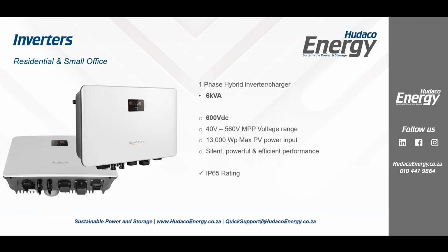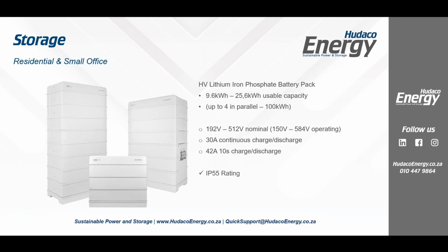600 volts DC, 2 inputs, 13 kilowatt peak, which is really fantastic. It's silent, it's powerful, and the performance is fantastic. Everyone that's got these units installed is seeing great yields on their systems. Okay. Then on the battery side, remember 9.6 kilowatt hours to 25.6 kilowatt hours is usable. In our particular case, on the 6 kVA single phase, it's 9.6 to 19.6, so about 20 kilowatt hours usable.